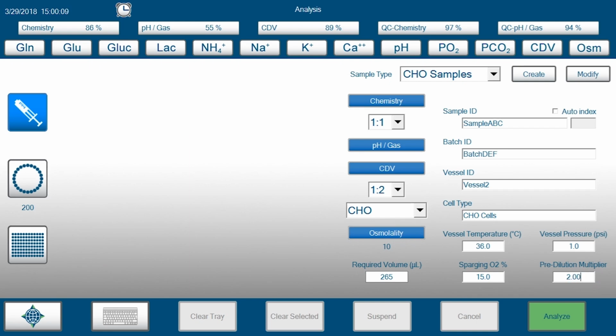Changing these values will only impact calculated pH, PO2, and PCO2 results, but all raw pH, PO2, and PCO2 results will still be reported based on the default values. These settings are sticky, so if one is changed, it will remain at the changed value until someone changes it again. It is important to note that the pre-dilution multiplier input only applies to results for the CDV module.